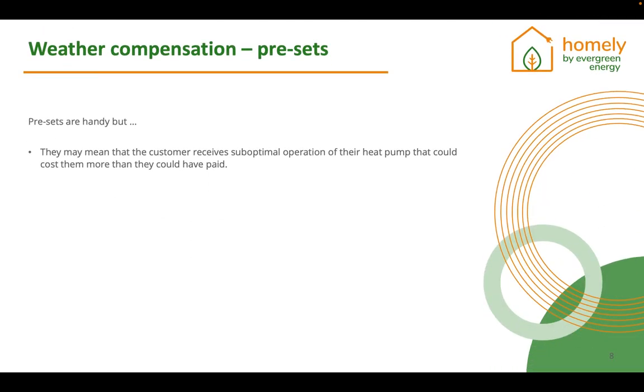We do believe that the presets are handy. So we have seen that some heat pumps come with a default weather compensation setup, which might be one for radiators and the other one for underfloor, and then you put on a third-party stat, which is on and off control on this system. We believe that does improve the efficiency of the heat pump compared to, for example, running the heat pump continuously at a fixed flow temperature of 55 degrees, but it still doesn't achieve the benefits of the heat pump that have been promised to the customer. So it doesn't achieve the faceplate COPs that we expect.